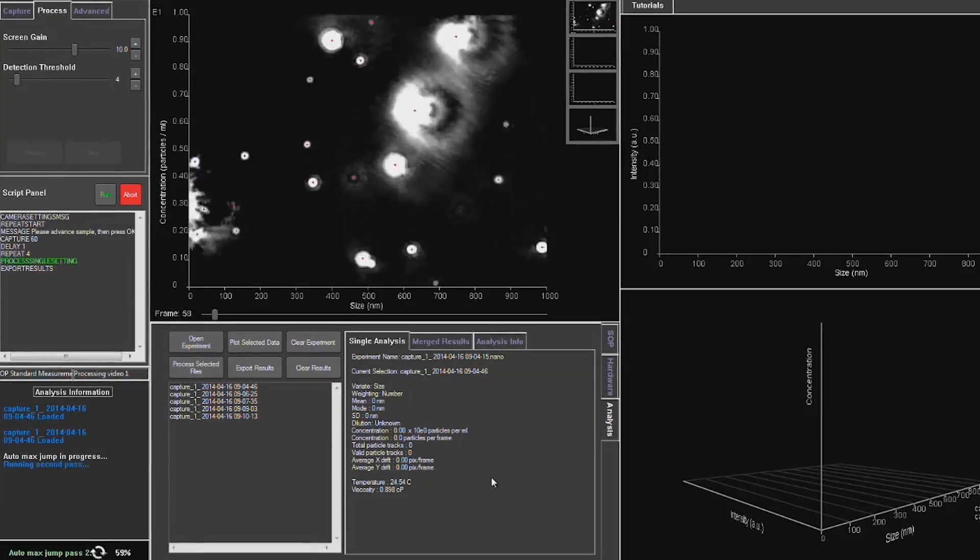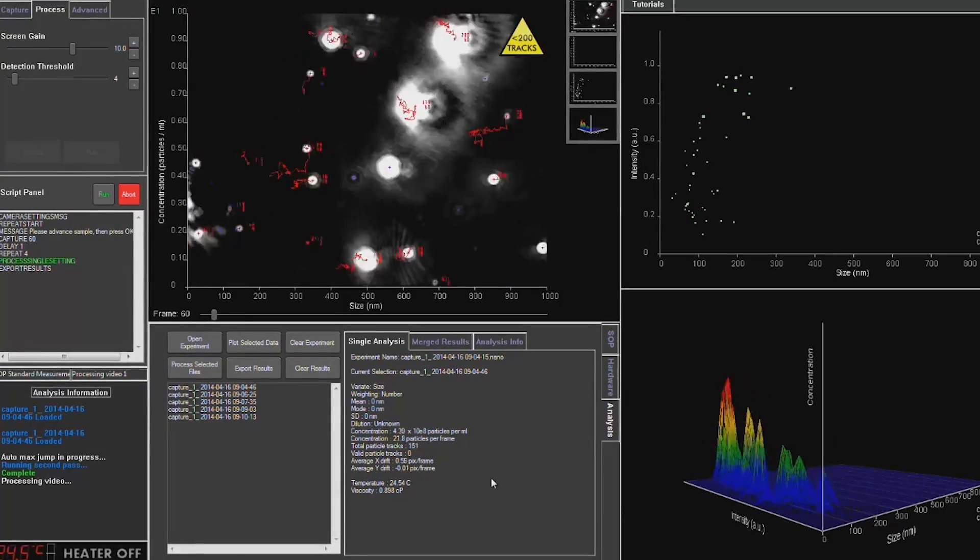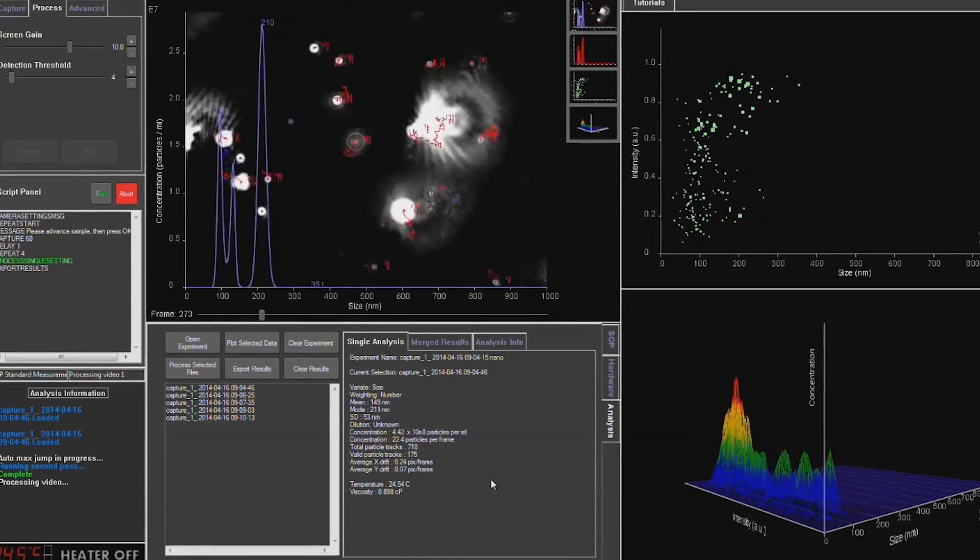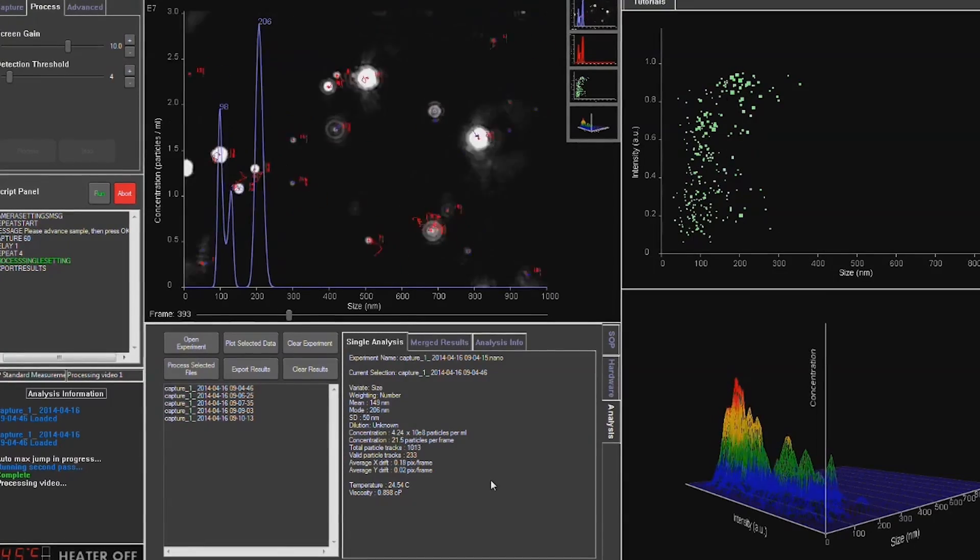All particles are tracked simultaneously, but because each particle is tracked individually, high-resolution number versus size distributions can be generated in minutes.